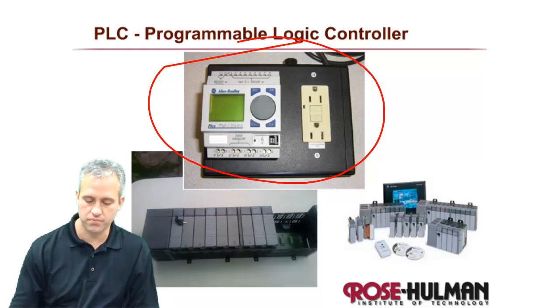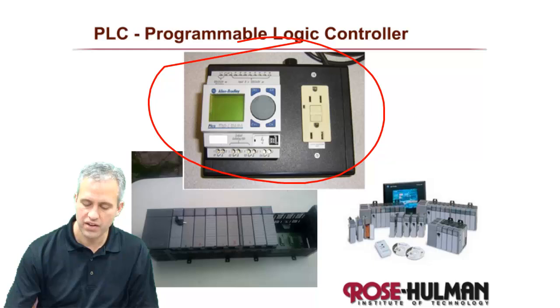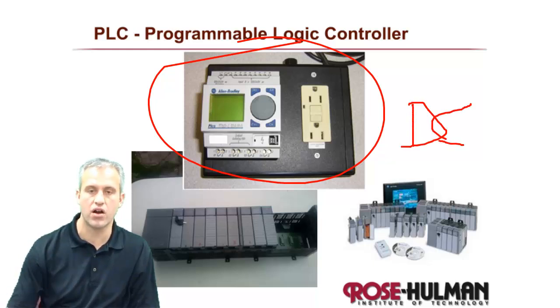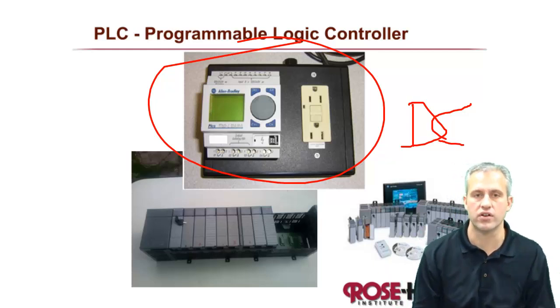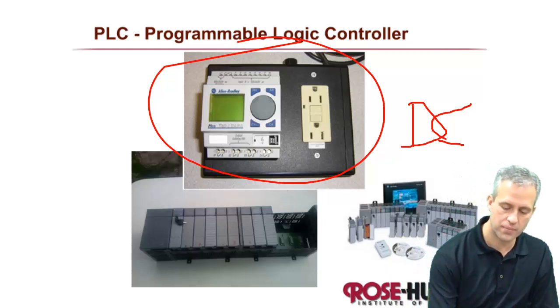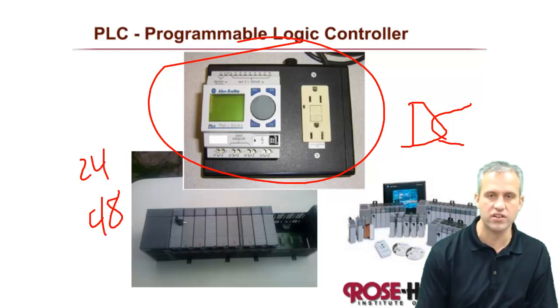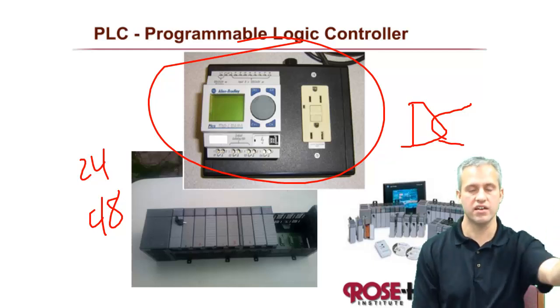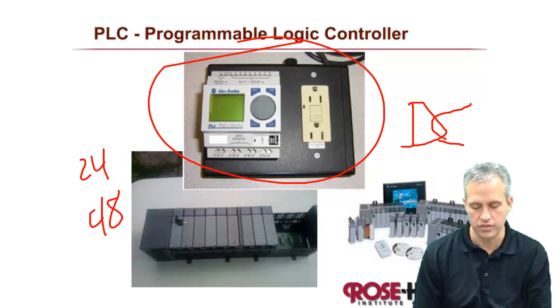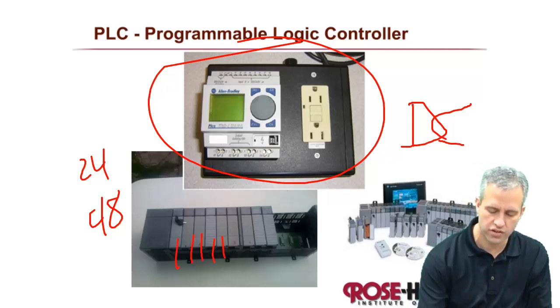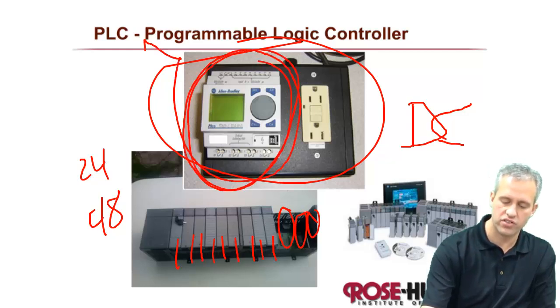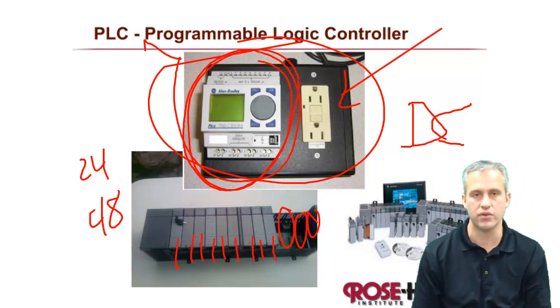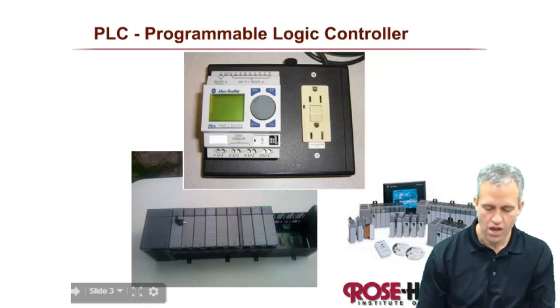There are different types of PLCs. The one we work with here is AC, but it is becoming fairly common to use DC PLCs. The reason is because it's hard to find good sensors that are AC — a lot of sensors these days work in the DC range. Even DC PLCs typically run at 24 or 48 volts DC, and the current is typically 10 to 100 times what we use with PICs. Some PLCs come in modules, so you can add more modules later, but the one we use is not modular — it just is what it is.